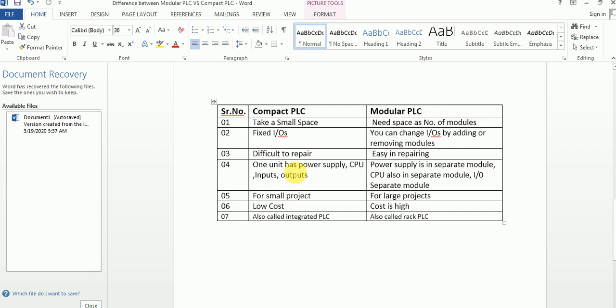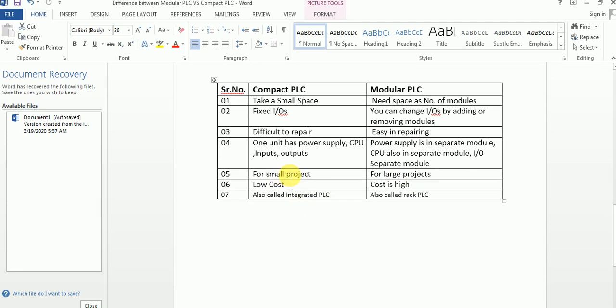As explained earlier, compact PLC has everything in one unit — power supply, CPU, inputs, and outputs. But in modular PLC, the CPU and other components are in separate modules. Compact PLC is used for small projects and its cost is low, while modular PLC is used for large projects and its cost is higher. Compact PLC is also called integrated PLC or small PLC.